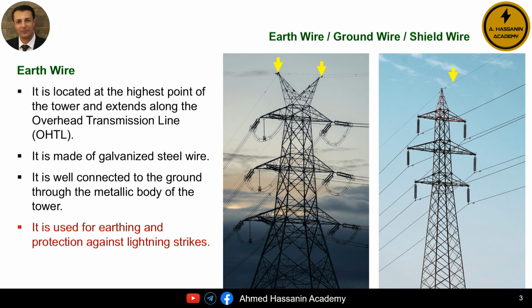I have previously mentioned that one of the main components or accessories of the overhead transmission line is the shield wire, earth wire, or ground wire, which is usually made of galvanized steel. I also mentioned that the earth wire is installed and positioned at the highest point on the tower of the overhead transmission line and extends along the entire length of the transmission line.